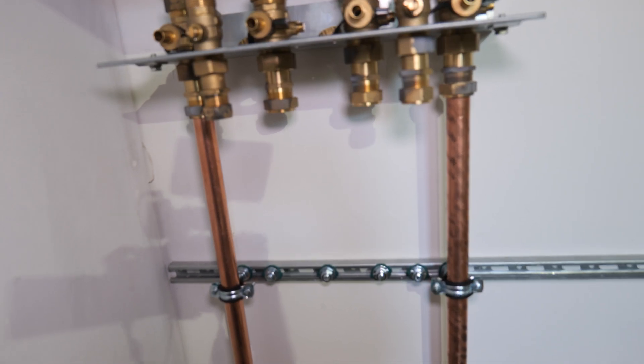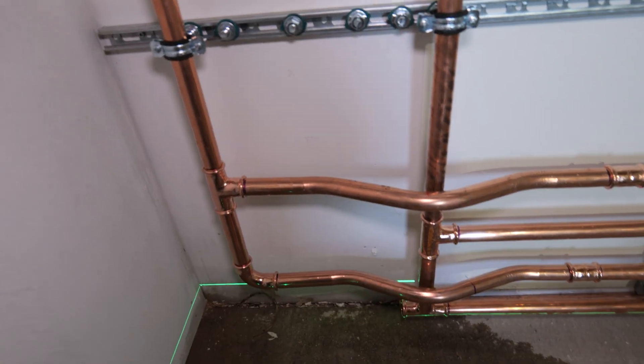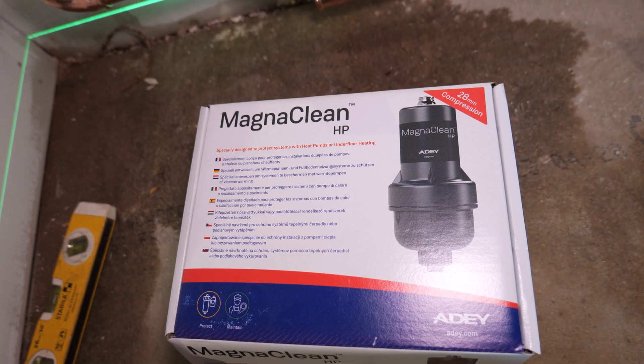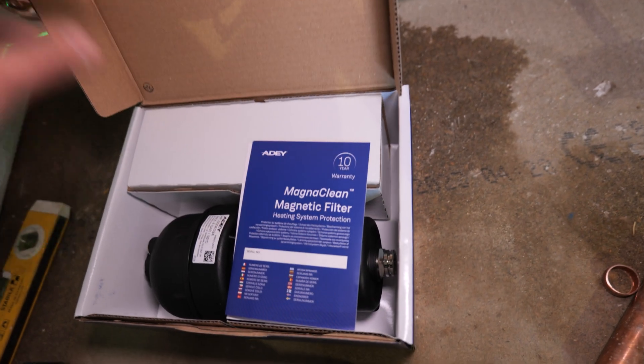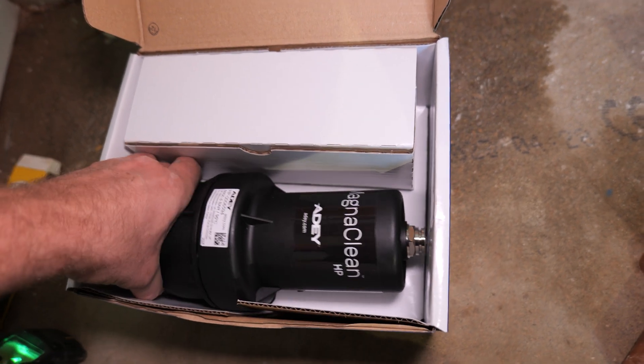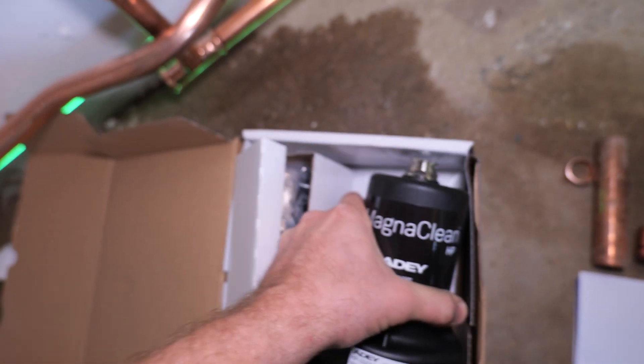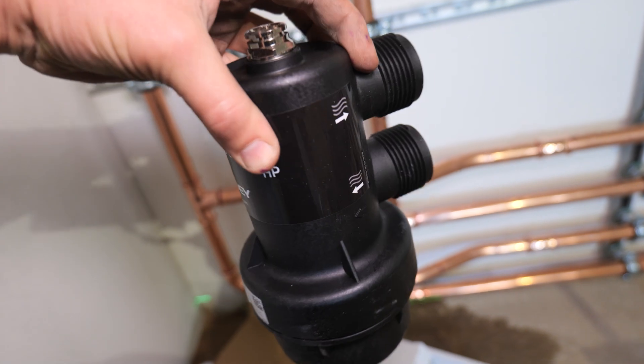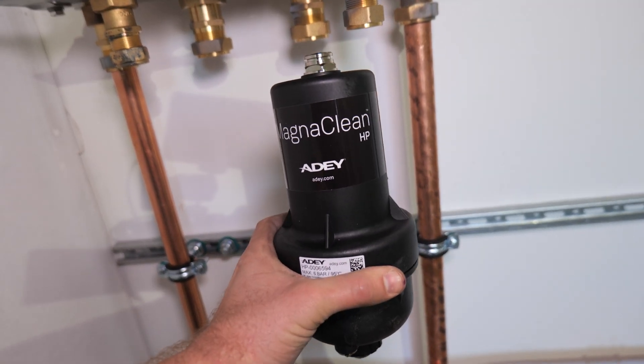I've also got an Adey MagnaClean filter this time rather than the Viessmann one. This is the Adey MagnaClean and it is heat pump specific — you can tell because it has HP marked on it. I've moved away from Viessmann filters mainly because the Adey ones are really brilliant. You can access the magnet quite simply and it's great for dosing. The main difference compared to the Professional II is it's a bit more bulky — they've had to increase the size to allow for the increased flow rate required for air source heat pumps. I'm going to mount it on the return going back to the air source heat pump, not on the return from the central heating.